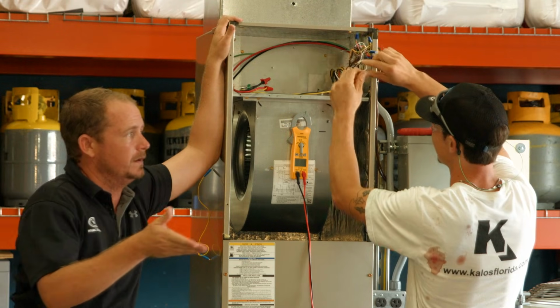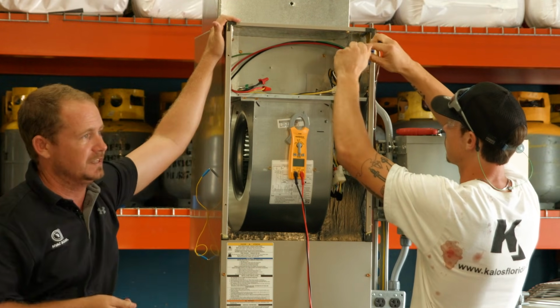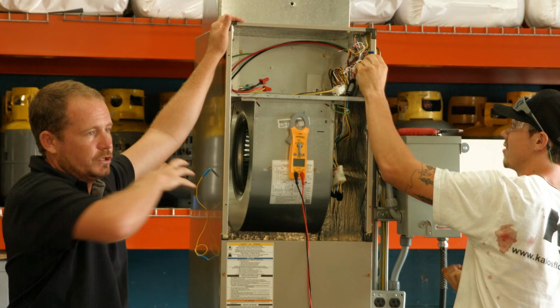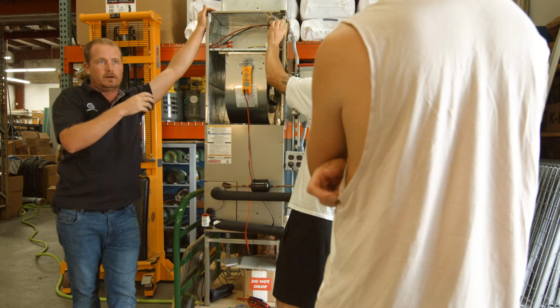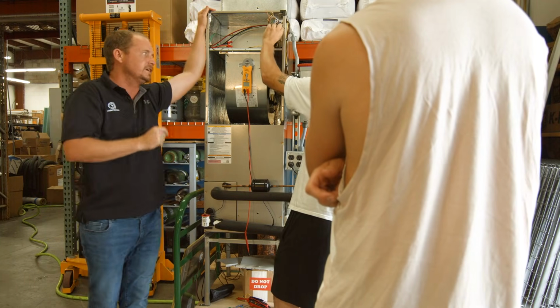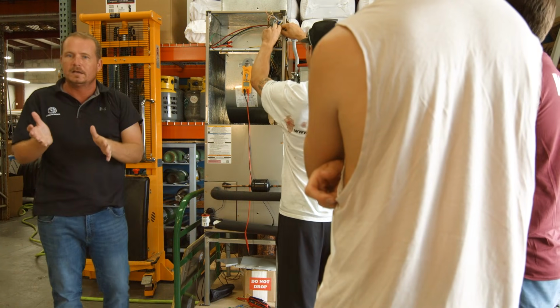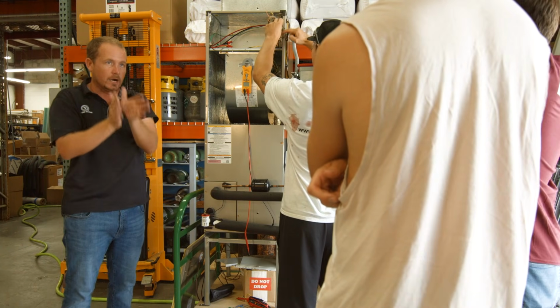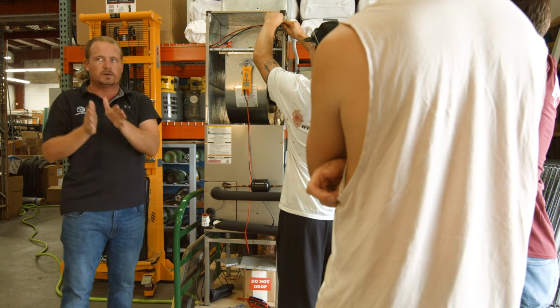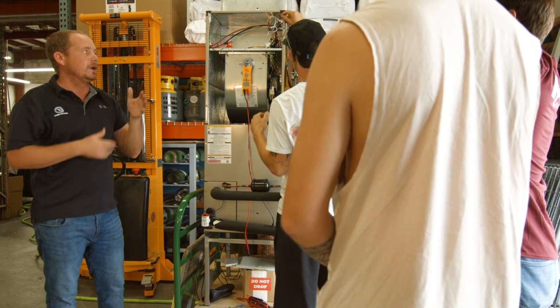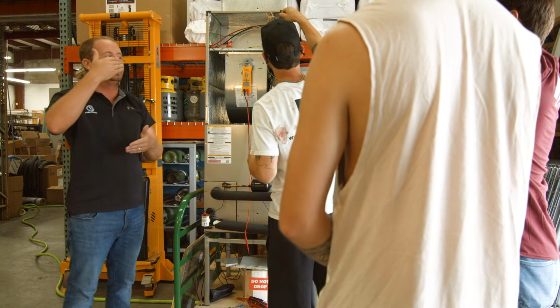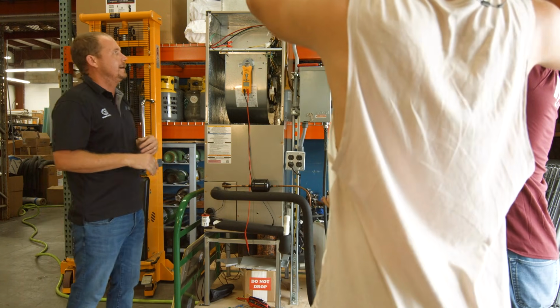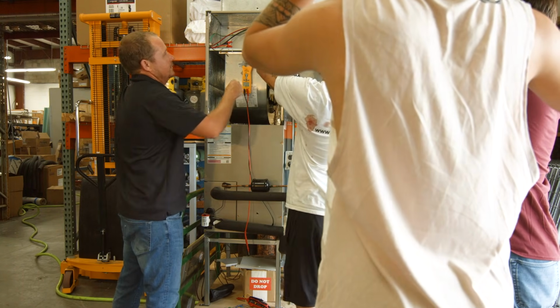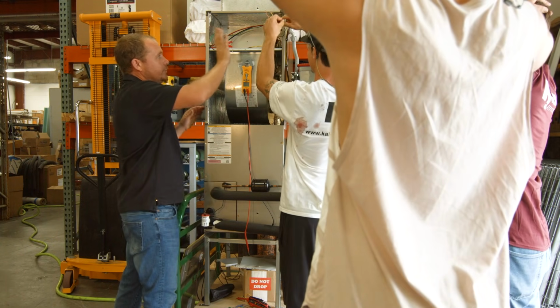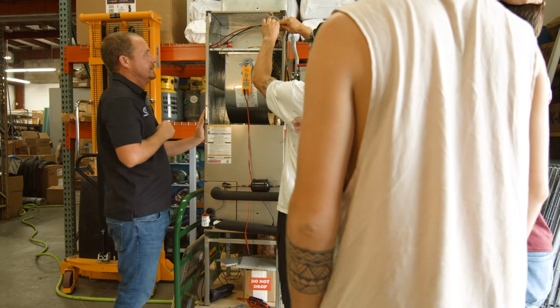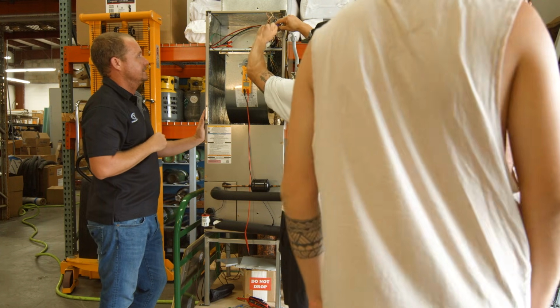So to Eric's point, and this just comes down to the irritation of disconnecting wire nuts, you could just pull the thermostat off the wall and do it there. So now you're jumpering each circuit, because what we're trying to find now is which circuit, which conductor is shorted, which conductor is tripping the breaker, right? Now we already know because we tested it the other way, but I just want to demonstrate how this would typically work. So now we have to, not the common though. Whenever you're doing this test, leave common completely connected and disconnect everything else.